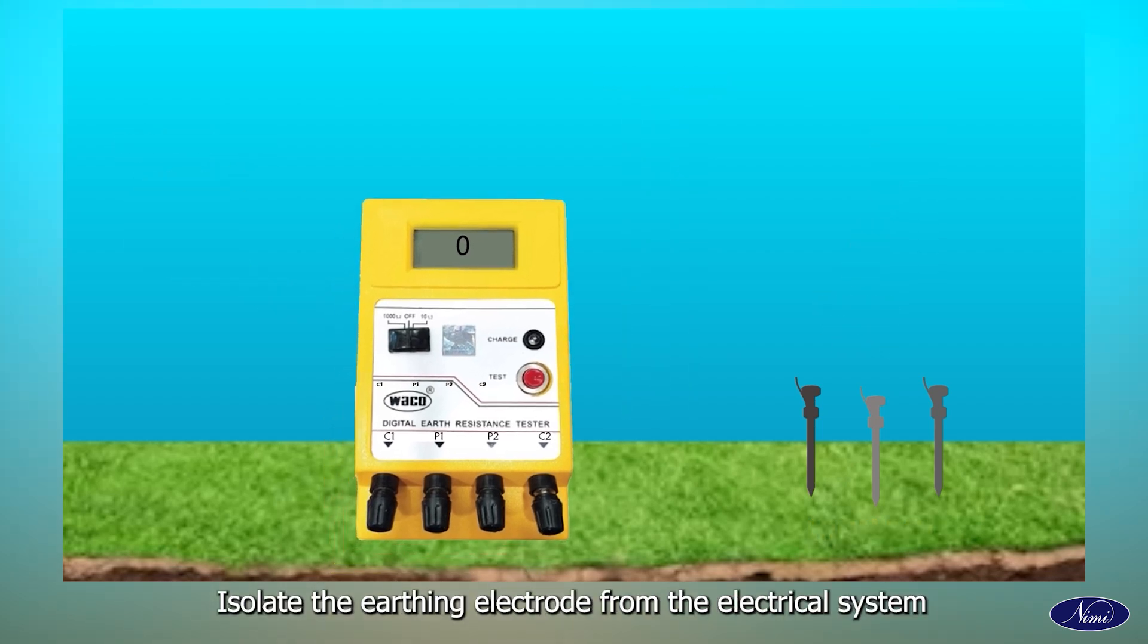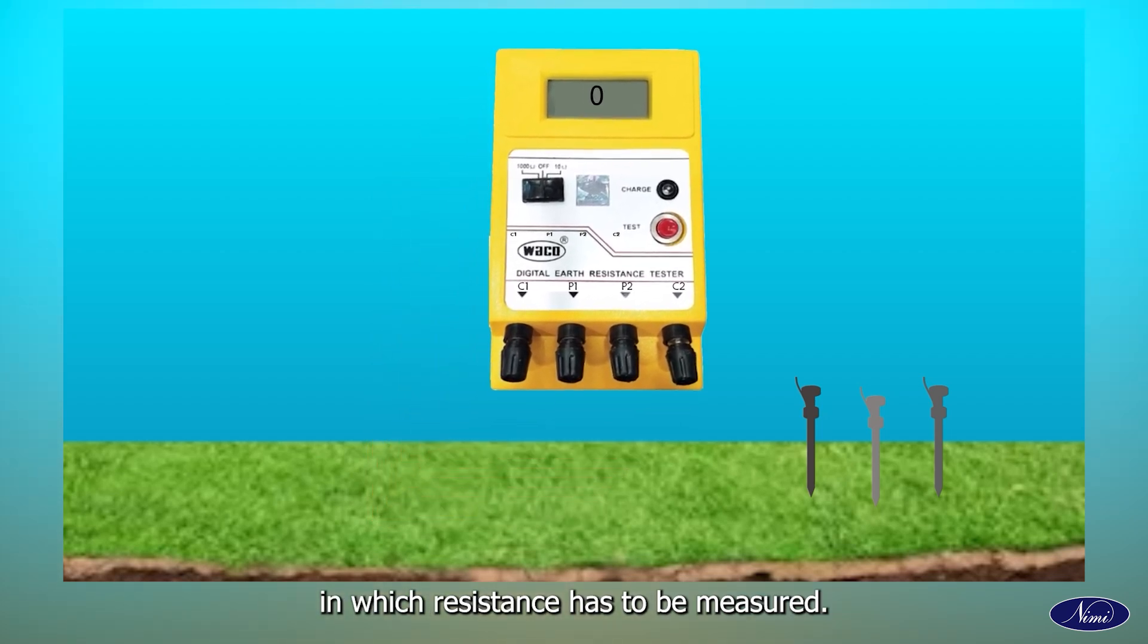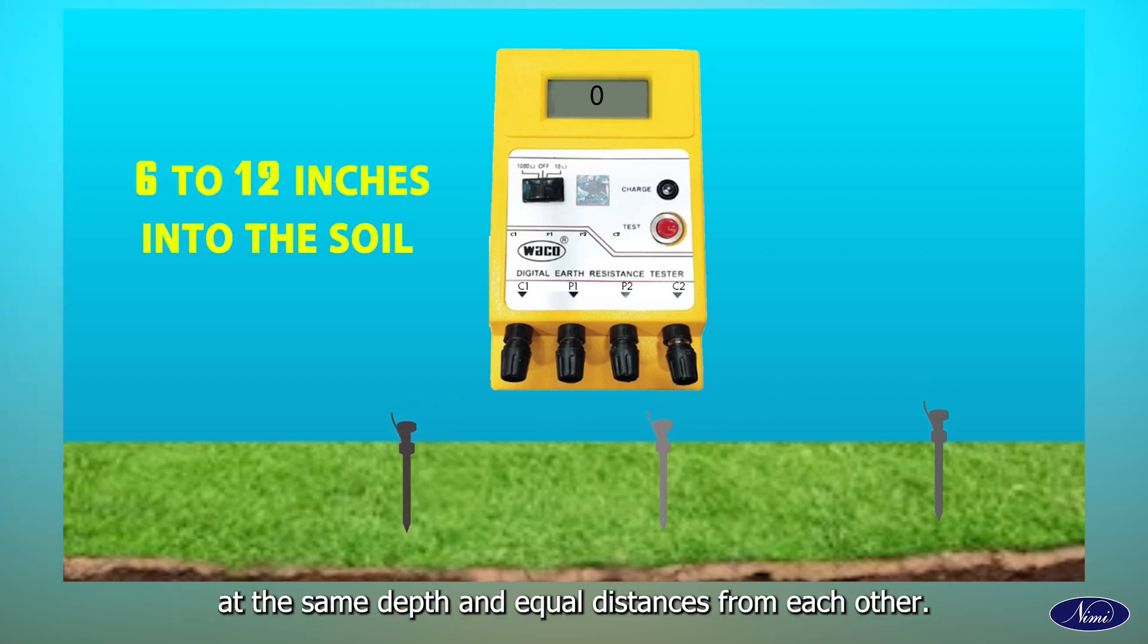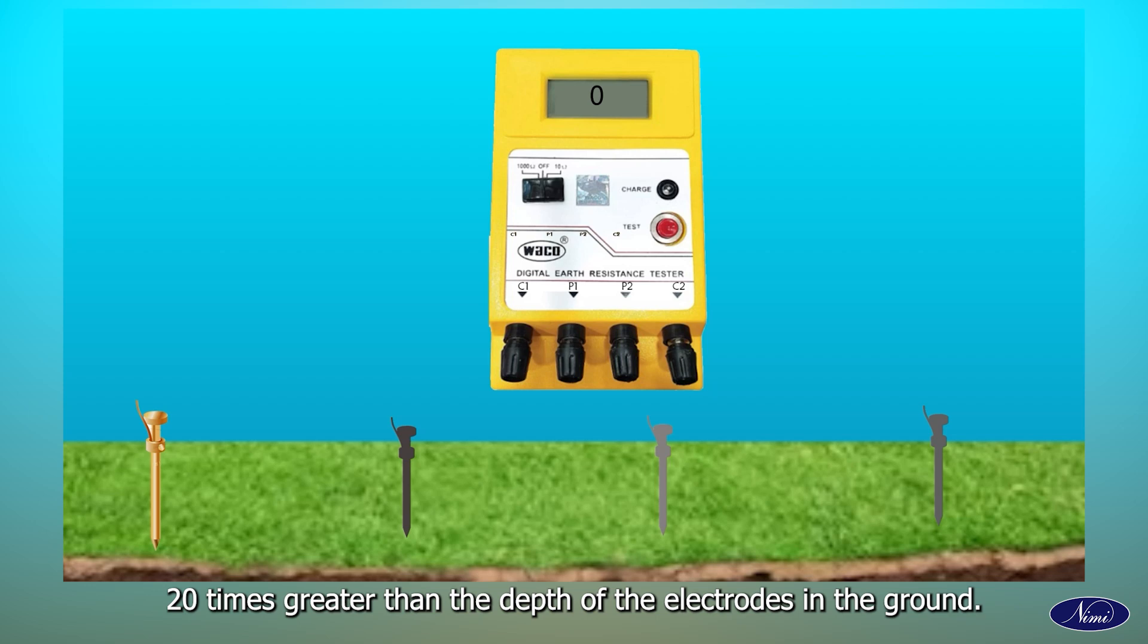Isolate the earthing electrode from the electrical system in which resistance has to be measured. Drive each electrode 6-12 inches into the soil at the same depth and equal distances from each other. The distance between Earth electrodes should be at least 20 times greater than the depth of the electrodes in the ground.